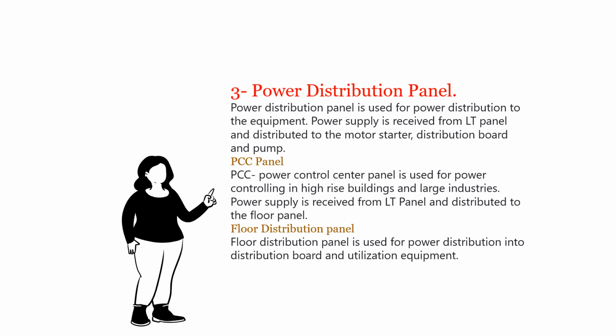Power distribution panel. Power distribution panel is used for power distribution to the equipment. Power supply is received from LT panel and distributed to the motor starter, distribution board and pump. PCC panel. Power control center panel is used for power controlling in high-rise buildings and large industries. Power supply is received from LT panel and distributed to the floor panel. Floor distribution panel. Floor distribution panel is used for distribution into distribution board and utilization equipment.